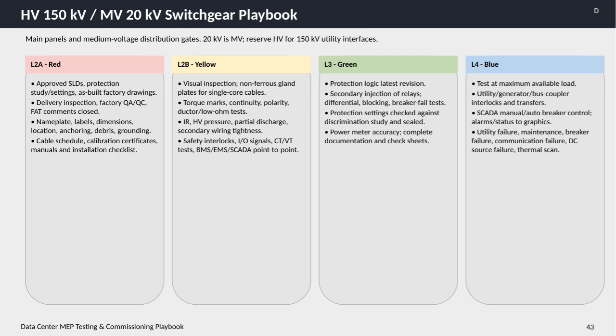Finally, L4 in blue covers full load testing and system integration. Tests are conducted at the maximum available load, and all interlocks and transfers involving utility, generators, and bus couplers are exercised. The SCADA system is tested for manual and automatic breaker control, as well as alarm and status visualization. This level also includes system responses for utility failures, maintenance conditions, breaker failures, communication losses, DC source failures, and thermal scans. Together, these layers ensure that the switchgear system is thoroughly tested, fully documented, and ready for reliable operation.